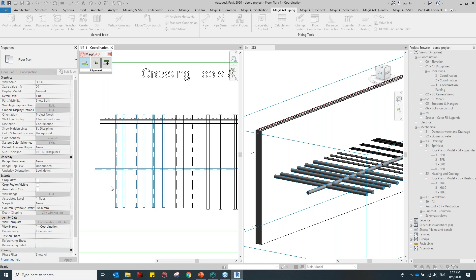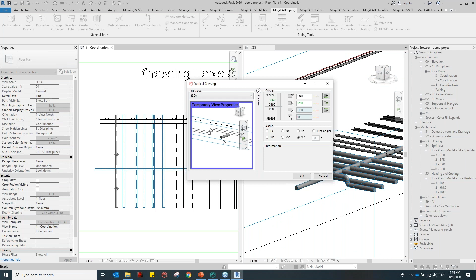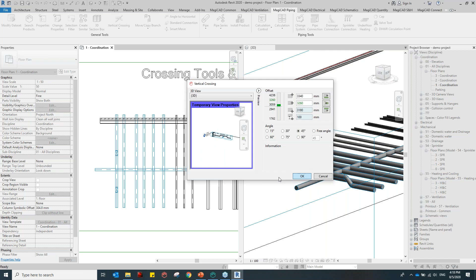For example, if I want to go with 90 degrees, the software says there is an error. Why? Because there is not sufficient gap between the two pipes. So I can adjust with a tolerance of 100 mm, then it will automatically make a connection with a 90 bend. You can see that. You can also preview in the toolbar as well, so once this satisfies your requirement, you can just click OK. It means you just specify where you want to cross, and it will automatically cross over for you.